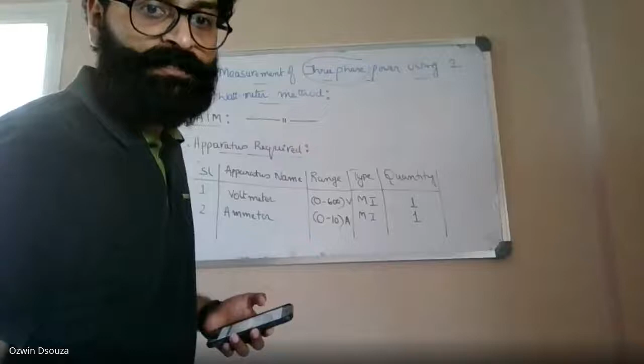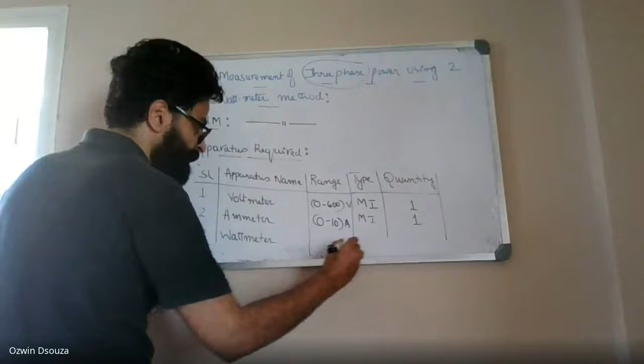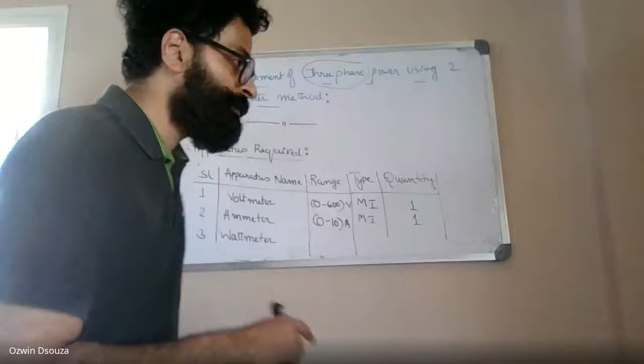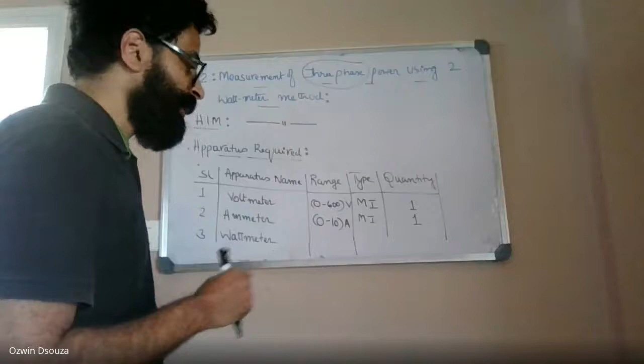And then you need a wattmeter. The wattmeter range is slightly different because your wattmeter is kind of a hybrid meter which has a current coil as well as a potential coil, so you have to describe both coil ranges. You can simply write 10 amperes, comma, 600 volt, UPF.